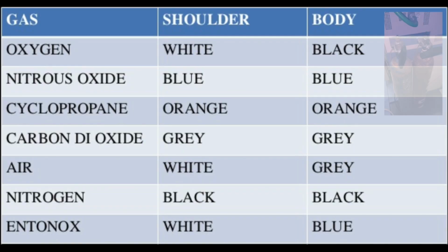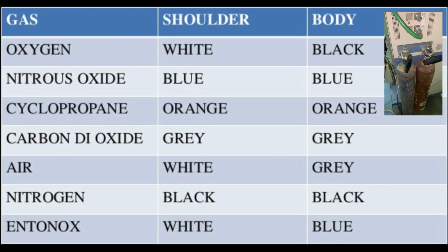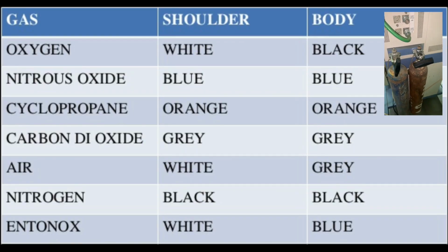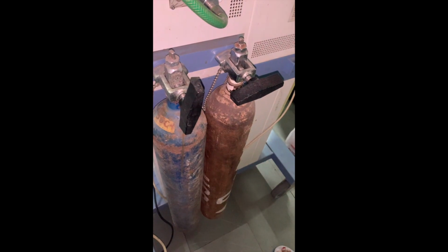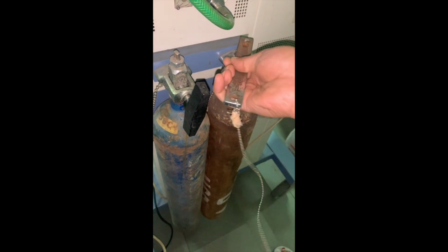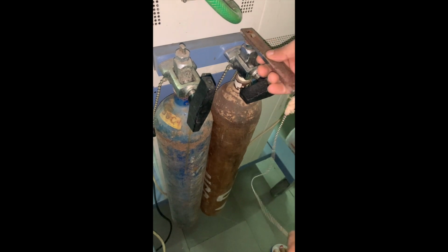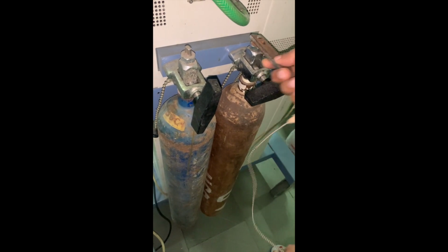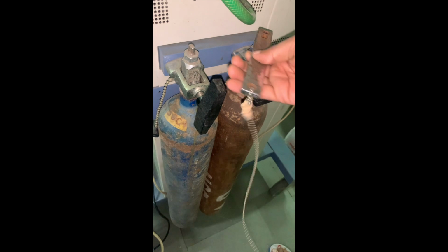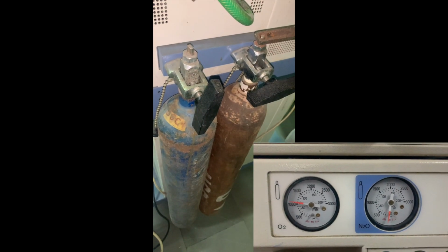Ensure that the correct cylinder is placed properly in the hanger yoke assembly and there is no leak. Open each cylinder and check for its pressure in the respective pressure gauge. The cylinders are to be opened in an anti-clockwise manner. This shows that a nitrous cylinder isn't having pressure.